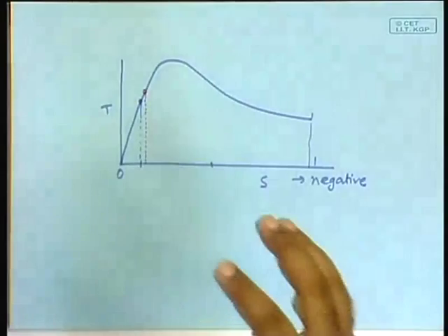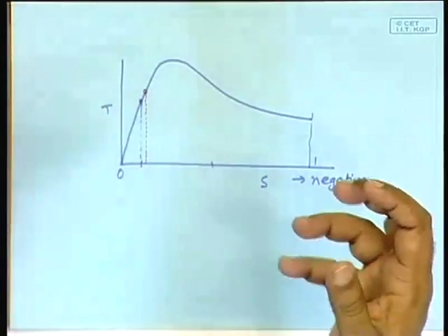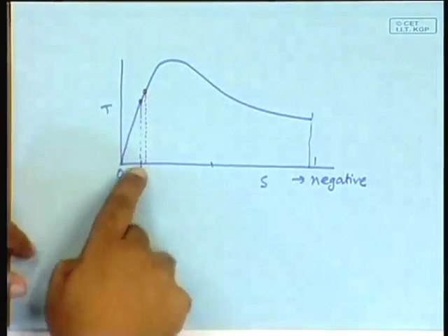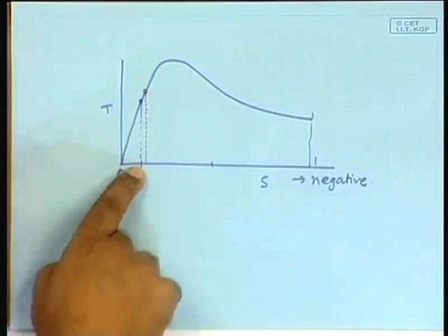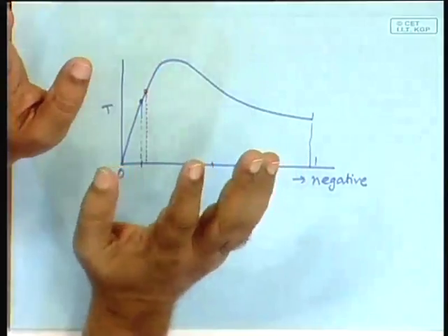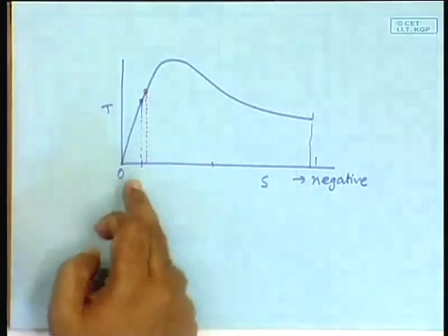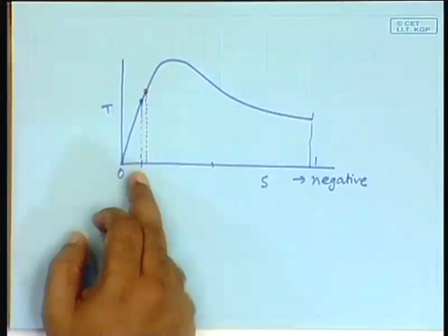The wind turbine was giving a certain amount of torque, and due to some reason the slip increased, and what has happened? The back torque has increased, right? A back torque has increased means it will slow it down. As a result, the slip will again come back to this value. Can you see that? There was a torque given by the wind turbine, and when it is working here, if somehow the slip is perturbed, then the torque is perturbed in the direction which will bring the slip back to its normal value. Is the statement clear? Which means this is a stable mode of operation.